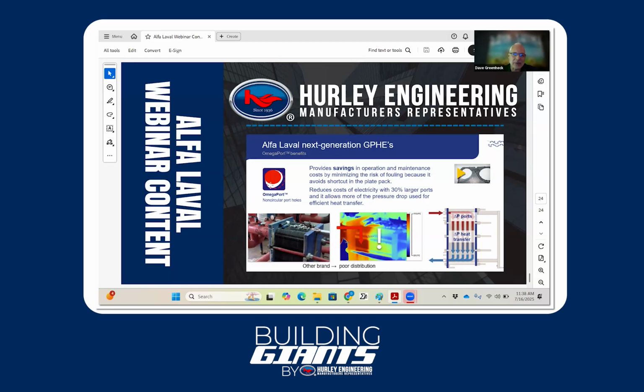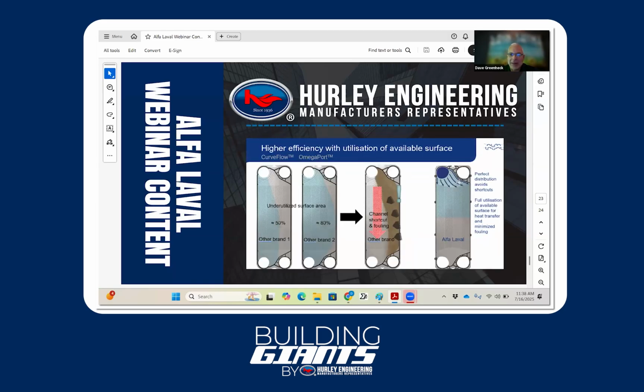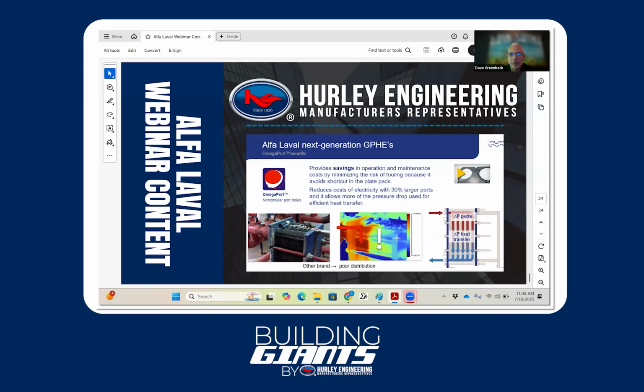If you notice the standard circle versus the omega port, it helps with two things. The curve pattern coming in with the omega port helps with the flow being evenly distributed across the plate, but it also helps to make sure all the plates get even distribution. So what you see with the omega port versus a standard circle is that the omega port is going to help make sure that you get even distribution along the entirety of that header. So it's not just getting the plate equal flow, but all the plates equal flow.